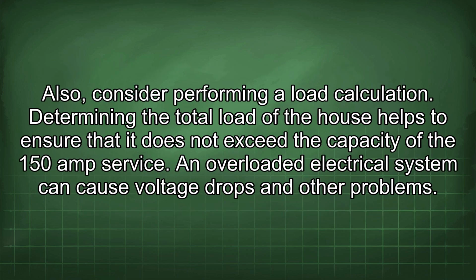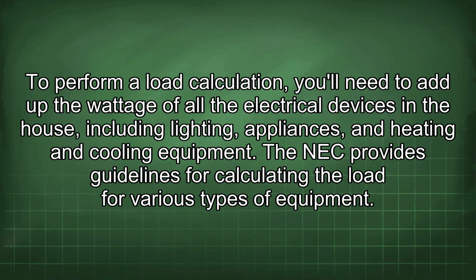Also, consider performing a load calculation. Determining the total load of the house helps to ensure that it does not exceed the capacity of the 150 amp service. An overloaded electrical system can cause voltage drops and other problems. To perform a load calculation, you'll need to add up the wattage of all the electrical devices in the house, including lighting, appliances, and heating and cooling equipment. The NEC provides guidelines for calculating the load for various types of equipment.